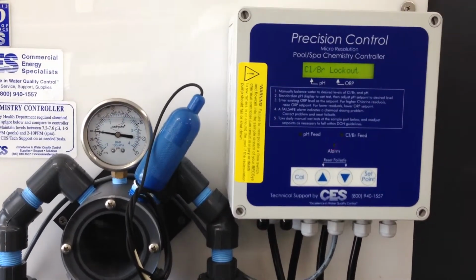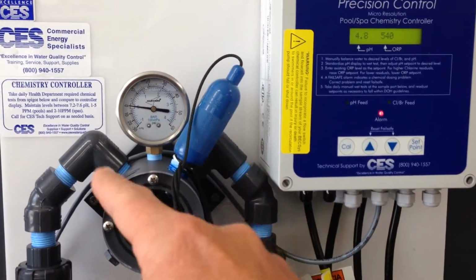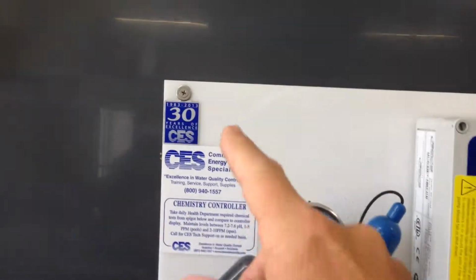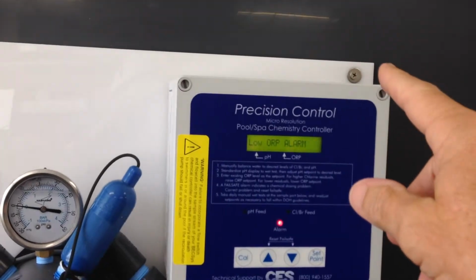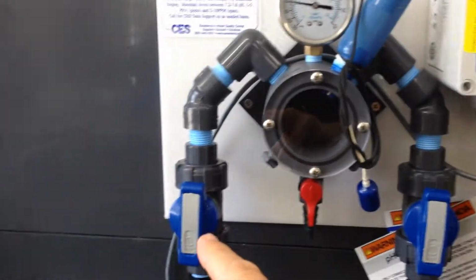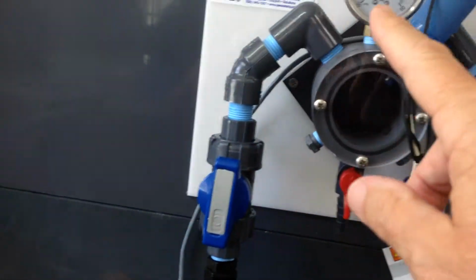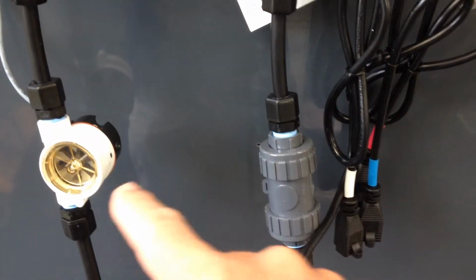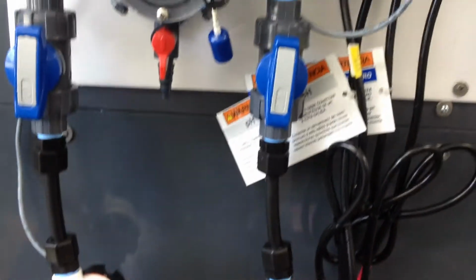So the number one job is you take it and you let the probes wet in, like we said. You will have mounted this to the wall, just like your normal system, and you're going to take water coming in from the flow from your sample stream. It should be filtered, but unheated water comes in through there, and normally we loop this back around and take it either to the surge tank or to the suction side of the pump. You'll see there's a check valve here, and that only allows the water to go one direction. So this is set up exactly the way you want.